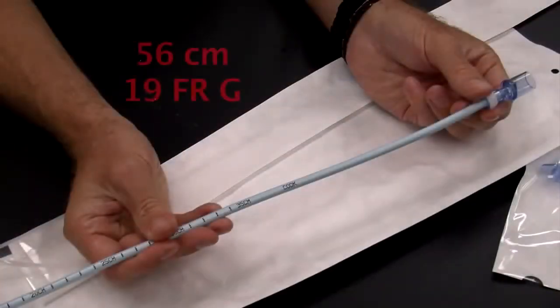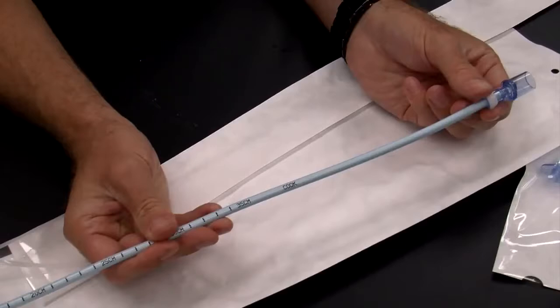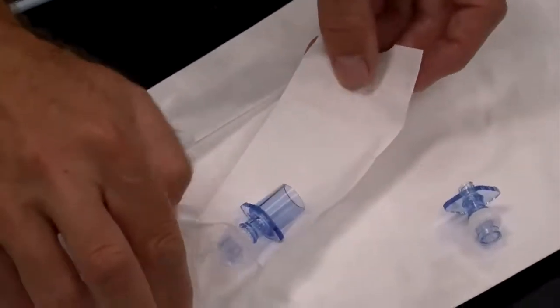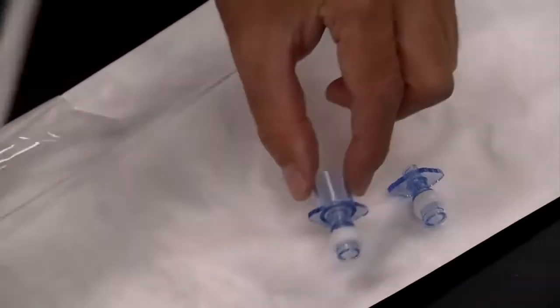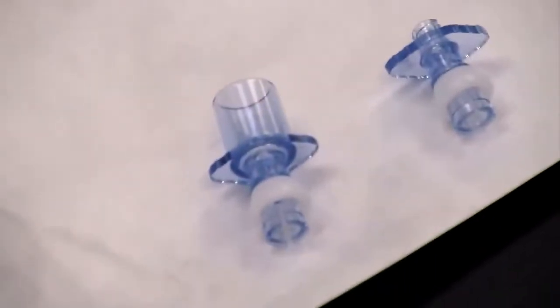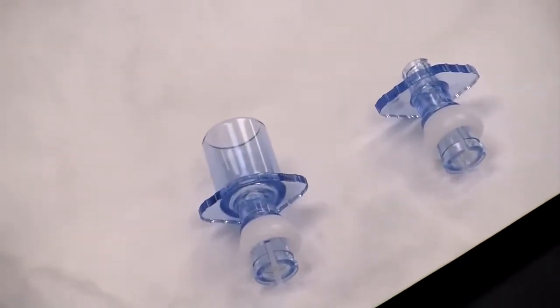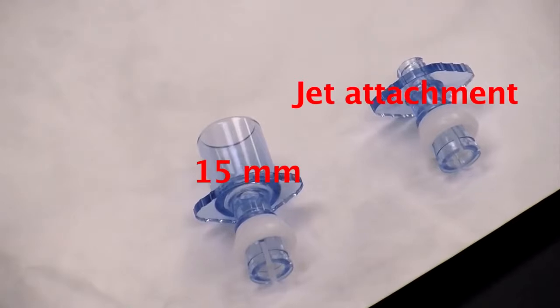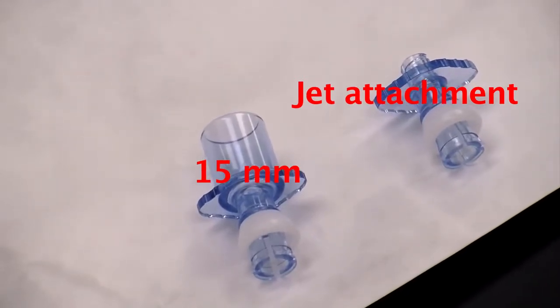The Aintree catheter is a 56 cm 19 French gauge semi-pliable catheter designed to accommodate a fibre optic scope, allowing the distal tip to remain uncovered and fully flexible to direct the scope and therefore the bougie into the glottis. The Aintree comes supplied with two RapidFit connectors, one for attachment to a standard 15 mm connector for bag and mask or circuit, and a connector for use with a jet ventilator.